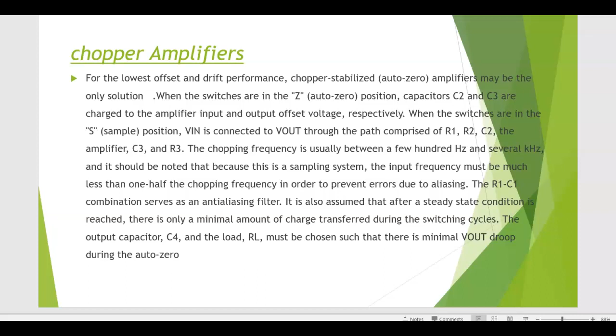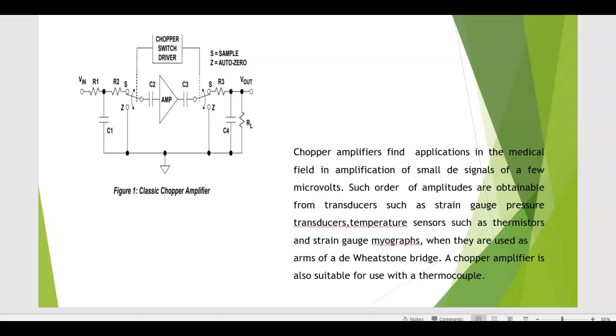This is the basic circuit diagram of the classic chopper amplifier. The chopper amplifier finds applications in the medical field in amplification of small signals of a few microvolts. Such orders of amplitude are obtainable from transducers such as strain gauges, pressure transducers, temperature sensors such as thermistors, and strain gauge myographs when they are used as arms of a Wheatstone bridge. A chopper amplifier is also suitable with thermocouples.